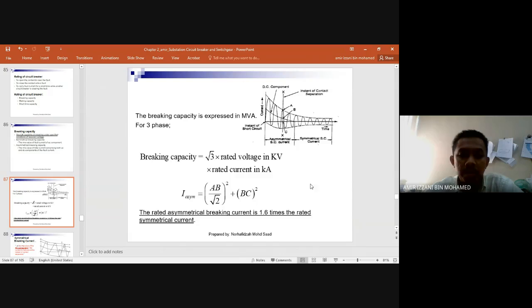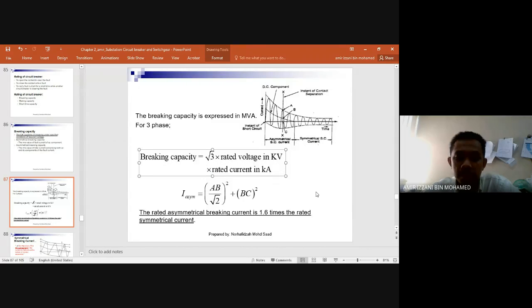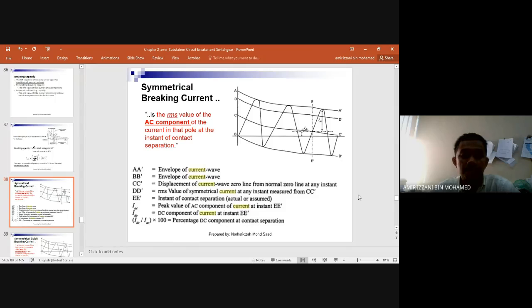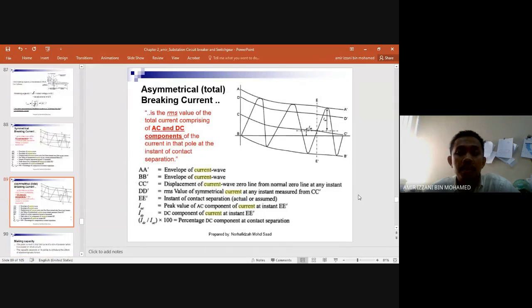So it's not symmetry. Okay, this is how to calculate the breaking capacity: √3 times the rated voltage in kV times the rated current in kA. The rated asymmetrical breaking current is 1.6 times the rated symmetrical current. And this is another illustration to show the difference between the symmetrical and asymmetrical components.